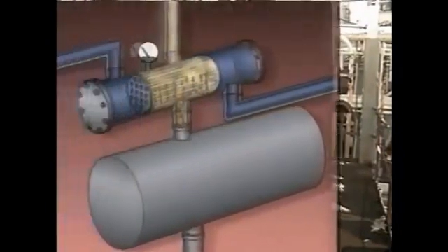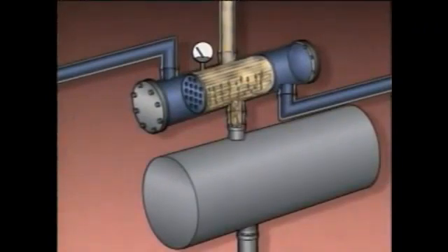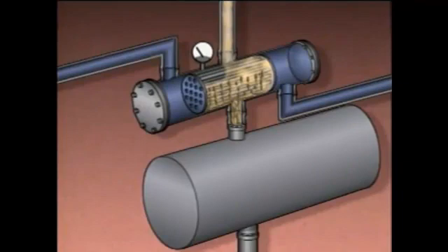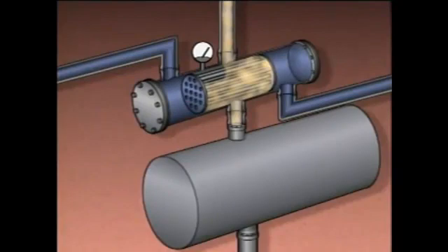Non-condensable gases can build up inside a condenser. When this happens, the gases insulate or blanket the tubes and reduce the amount of heat transferred in the condenser. As a result, less vapor will condense, and the pressure inside the condenser will increase. The increase in pressure may reduce the flow of vapor, or it could stop the flow altogether.